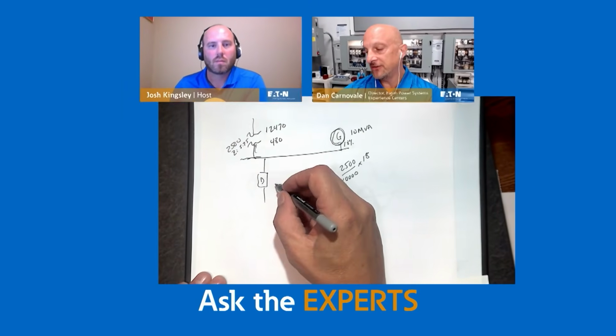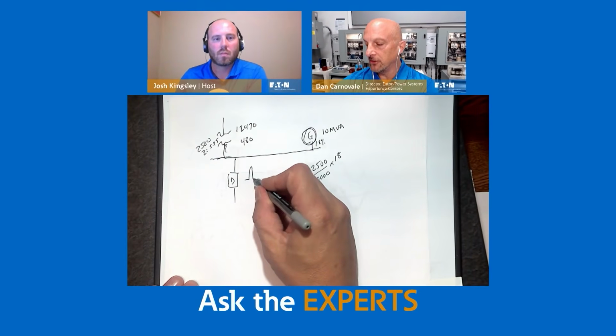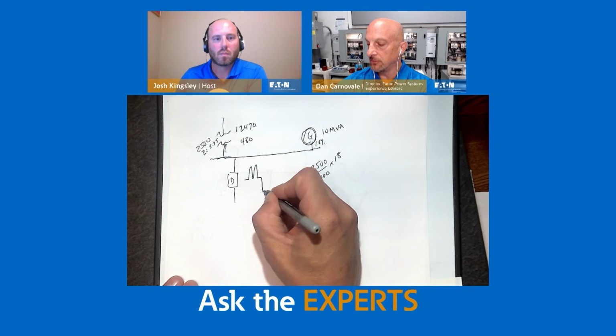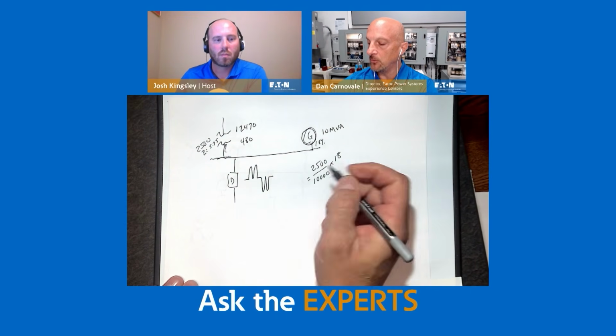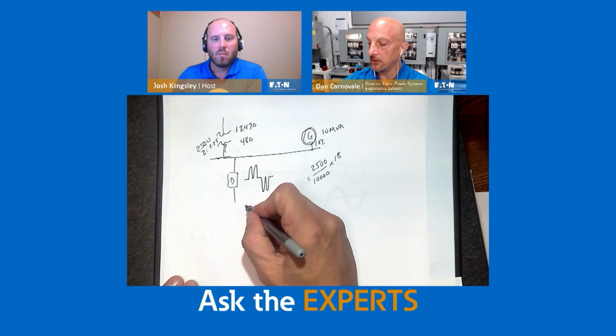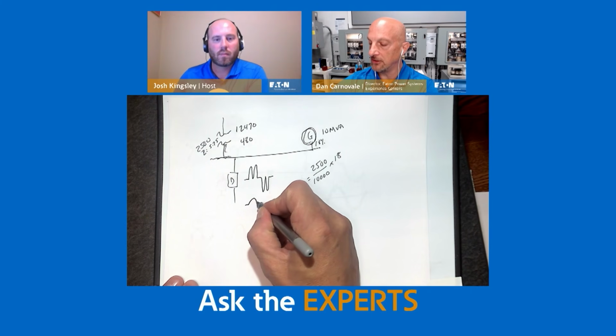Now, the other thing that could happen is, let's say this generator is very small. The current from this is actually an interesting phenomenon that happens. The current from the system could look like this when you look at the harmonics on the drives. And then when it's run on the generator, if it has really, really high impedance, it actually could look like this.